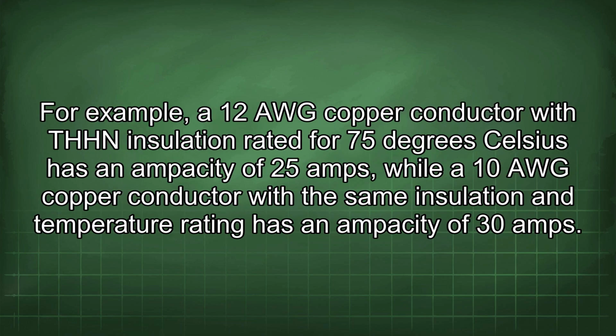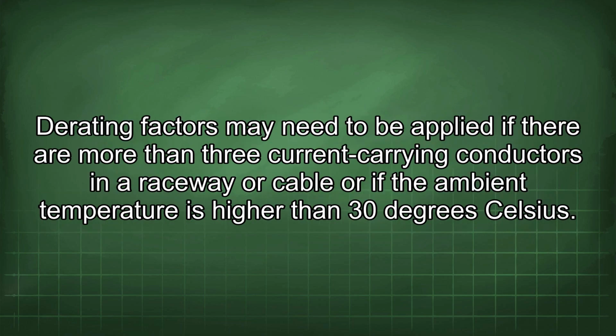For example, a 12 AWG copper conductor with THHN insulation rated for 75 degrees Celsius has an ampacity of 25 amps, while a 10 AWG copper conductor with the same insulation and temperature rating has an ampacity of 30 amps. Derating factors may need to be applied if there are more than 3 current-carrying conductors in a raceway or cable, or if the ambient temperature is higher than 30 degrees Celsius.